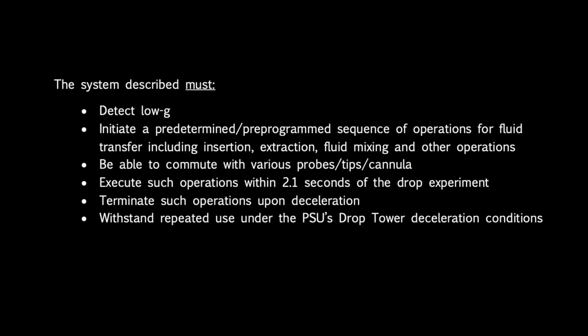Our sponsor, IRPI, indicated that the system we design must be able to detect low G and initiate a pre-programmed sequence of operations for fluid transfer, including fluid insertion, extraction, mixing, and other future operations. The system must be able to commute with various probes, tips, and cannula, and must complete test operations within the 2.1 second test window. The system must be able to terminate operations upon deceleration and withstand repeated use under PSU's drop tower deceleration conditions.